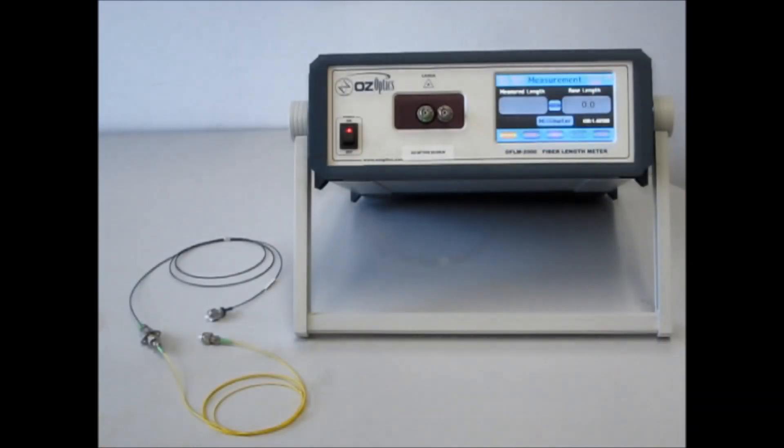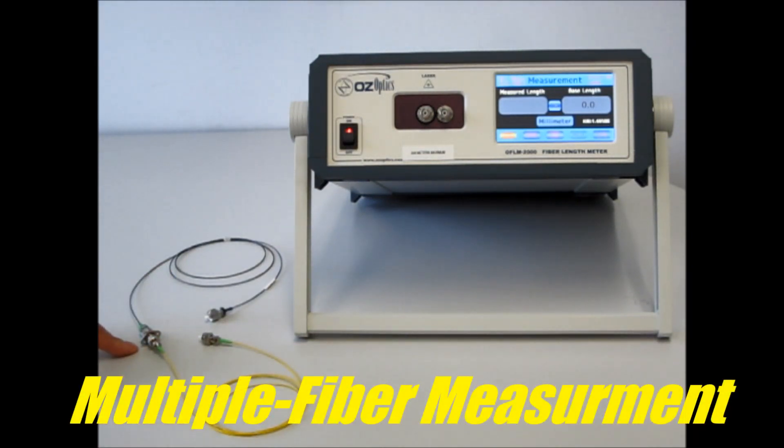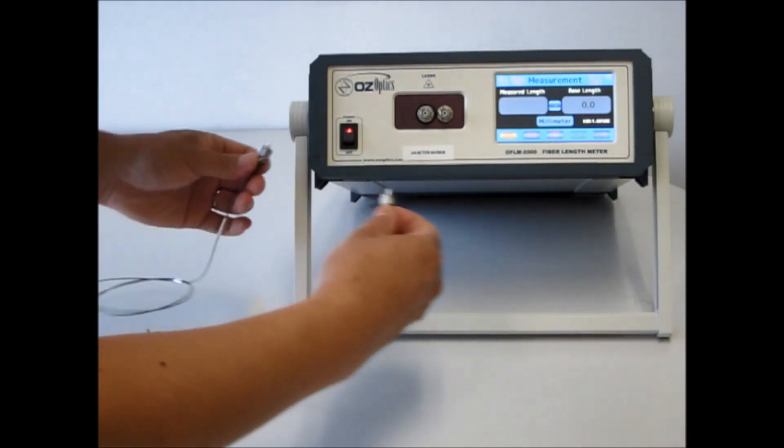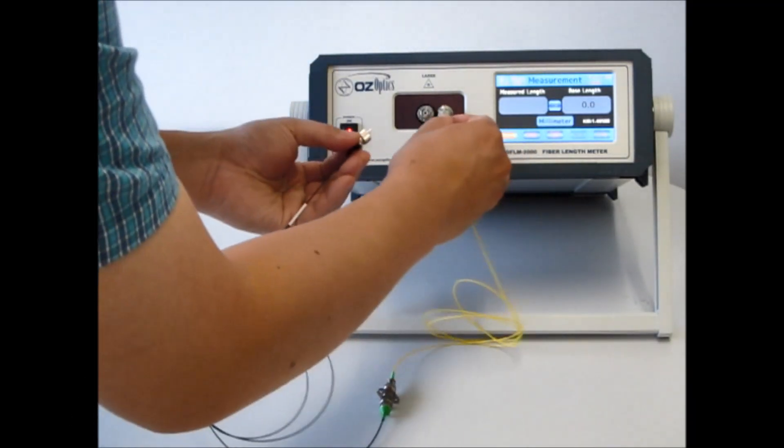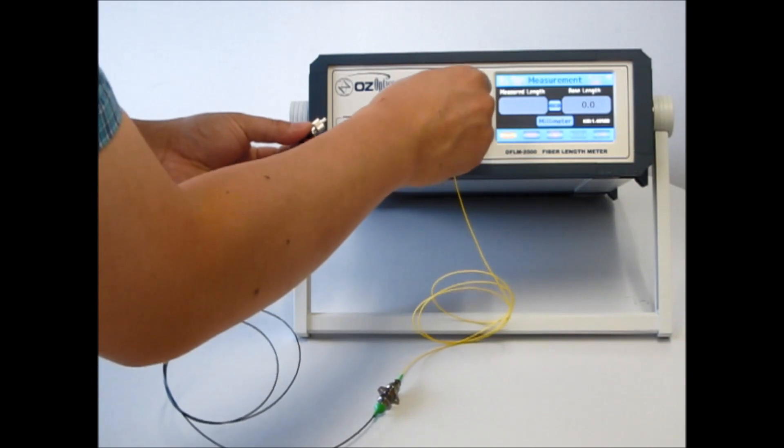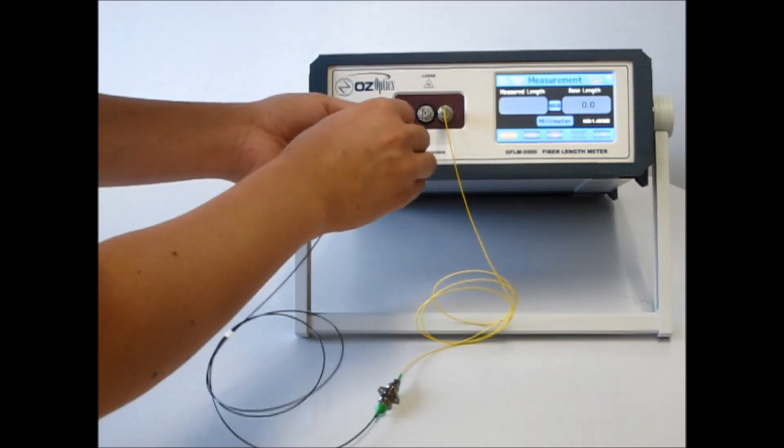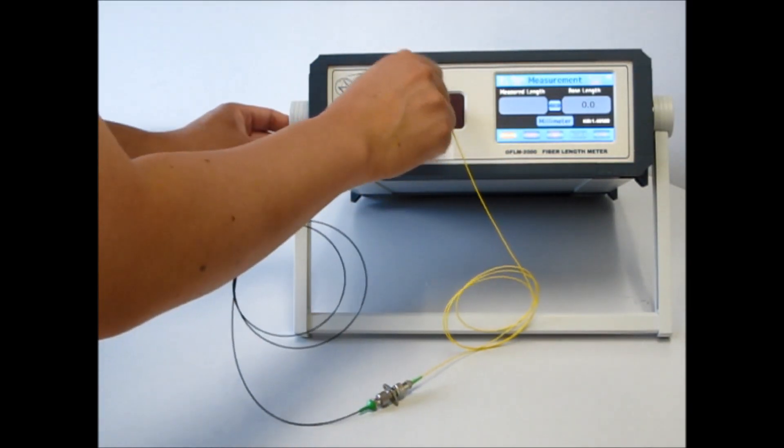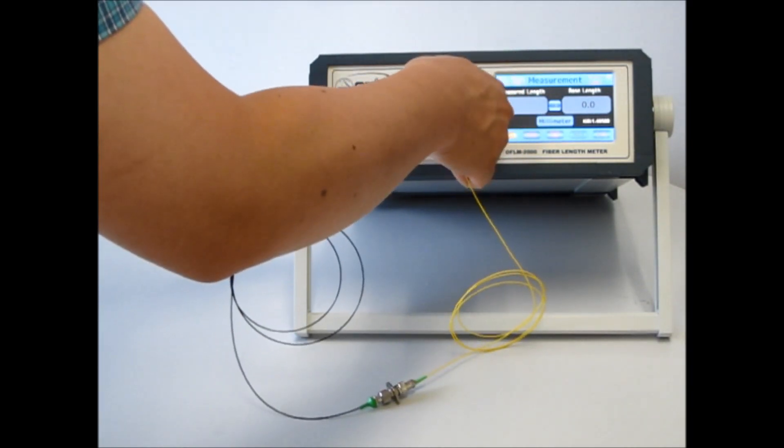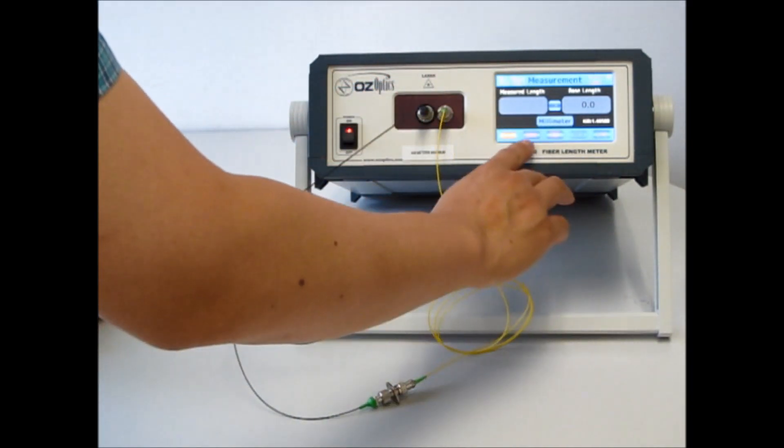The fiber length meter is a very robust measurement system. Here again, I have the two different patch cords from earlier, and I've connected them together using a sleeve-through adapter. Let's plug this in. Again, one end on the receive port and one end on the send port. Let's tighten up the connections and push the run button.